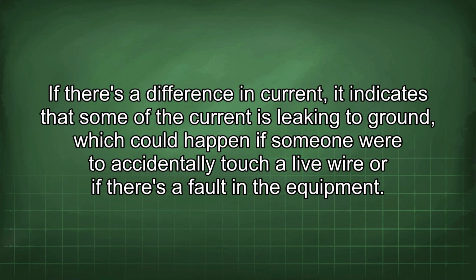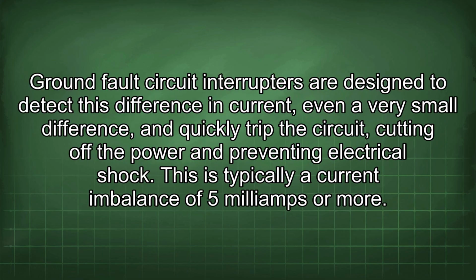If there's a difference in current, it indicates that some of the current is leaking to ground, which could happen if someone were to accidentally touch a live wire or if there's a fault in the equipment. Ground fault circuit interrupters are designed to detect this difference in current, even a very small difference, and quickly trip the circuit, cutting off the power and preventing electrical shock. This is typically a current imbalance of 5 milliamps or more.